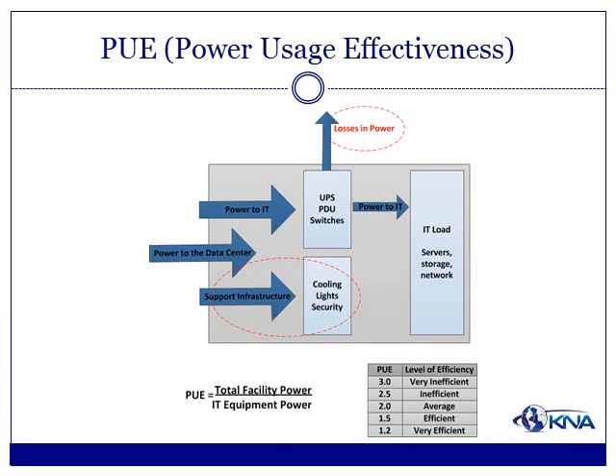A major driving factor in data center design today is efficiency. The standard metric for measuring efficiency in the data center environment is Power Usage Effectiveness, or PUE. PUE compares a facility's total power usage to the amount of power used by the IT equipment. This reveals how much is lost in distribution, cooling, and conversions. An ideal PUE is 1, but that is not realistic. An average PUE is around 2. We use PUE as a variable during the design process, and in addition, we can perform an audit of the data center to determine what the current PUE is.